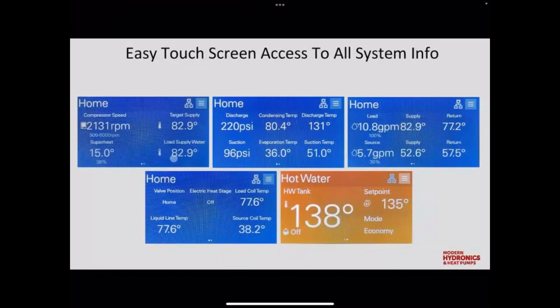In the home setting, the blue screens are all space conditioning screens, and the orange screens are hot water mode. You can see things like compressor speeds, the target supply, whatever we're shooting for at that moment, and the superheat. Then we can see the load supply water temperature, discharge pressure and suction pressure, condensing temperatures and evaporation temps, actual temperatures of the suction line and discharge, and all the information about the load and source water flows: supply and return temps, gallons per minute, pump speeds, and all that sort of information. All of this is readily available on the screen, in real time.